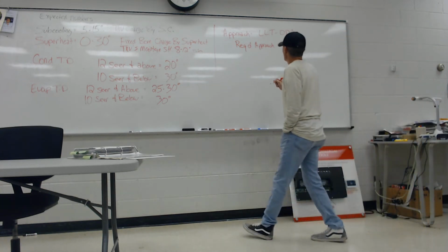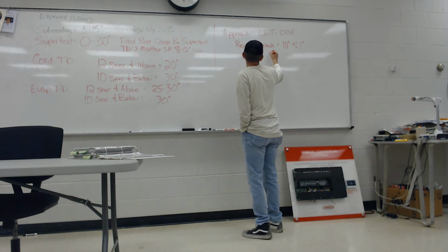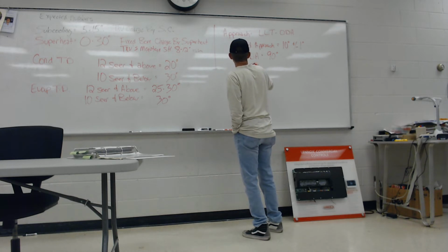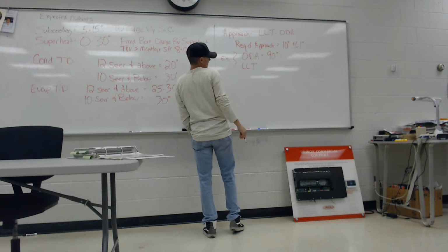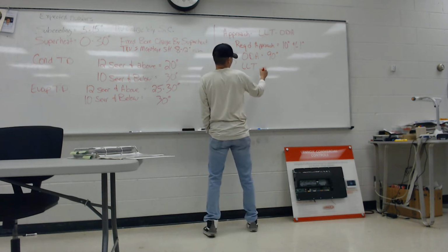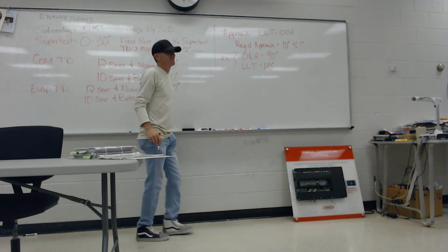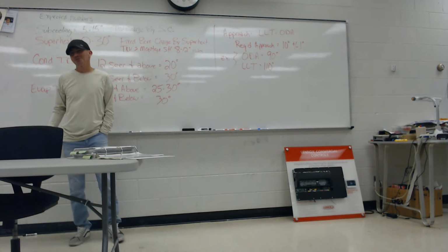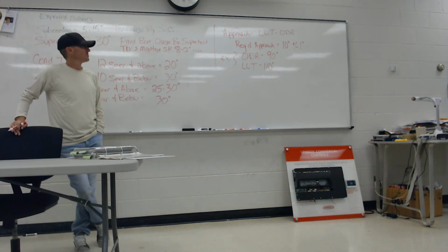Let's say the outdoor air temperature is 90 degrees and my liquid line temperature, this is just an example, is 110. Do some math. What's my approach? 20.